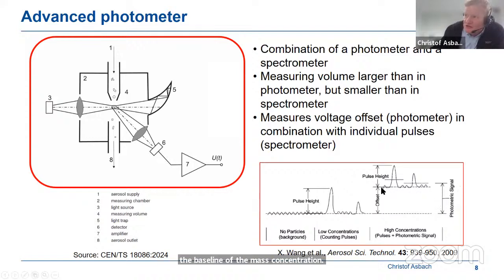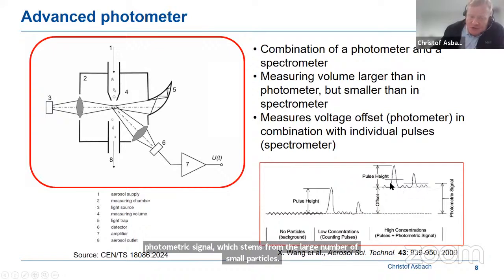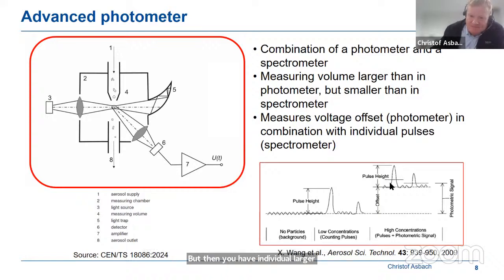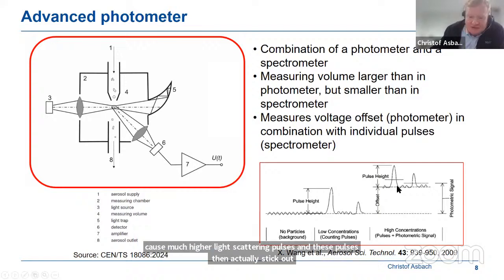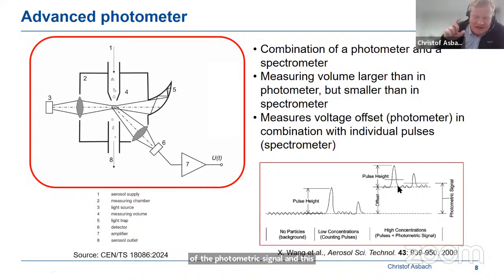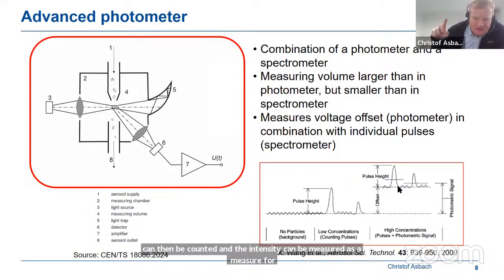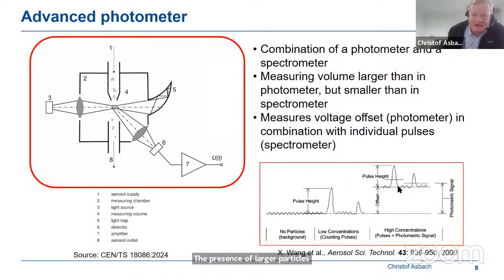So it measures the photometric signal, which stems from the large number of small particles. But then you have individual larger particles, a low number of individual larger particles. They cause much higher light scattering pulses. And these pulses then actually stick out of the photometric signal, and these spikes can then be counted, and the intensity can be measured as a measure for the presence of larger particles, and also the size can be estimated based on the height. And based on this, they can differentiate between different size fractions in terms of the mass concentration. And some also give different values or different fractions of the number concentration.